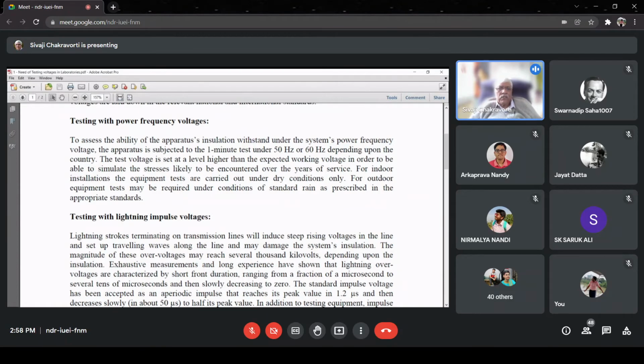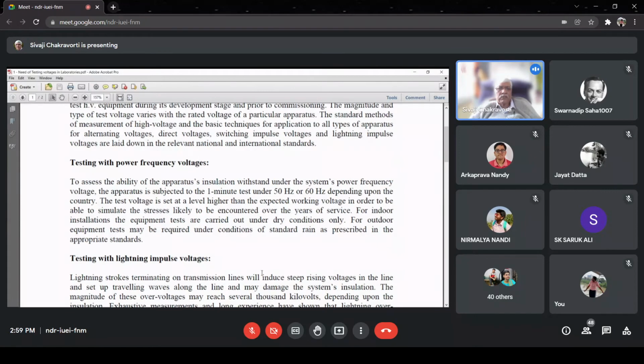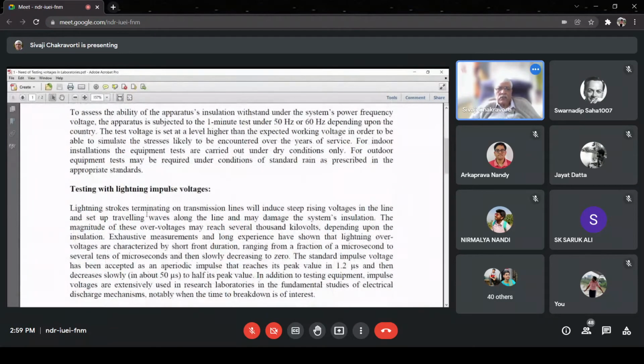If you look at this very short 2-page note, I am telling you that we need to test with power frequency voltages, and then we need to test with lightning impulse voltages. Then what is the difference between these two? There is a big difference. The difference is the wave shape of the impulse. I will talk about that in this class in detail. That is the important aspect: I have to generate a very specific wave shape in our laboratory for performing the test on the equipment.